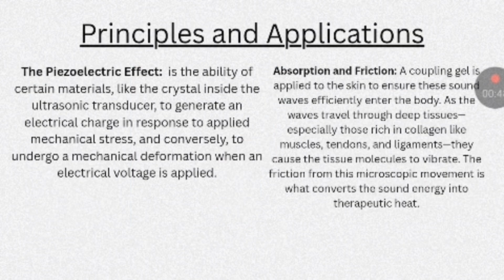The principle and applications. Primarily, the ultrasonic diathermy works on the principle of piezoelectric effect. It is the ability of certain materials, like the crystals inside the ultrasonic transducer, to generate an electrical charge in response to applied mechanical stress, and conversely, to undergo a mechanical deformation when an electric voltage is applied.